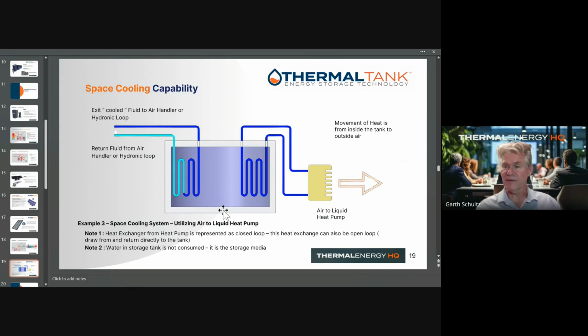And additionally, the buffering in the system allows the heat pump or the chiller that's operating and the air handling unit, it gives buffering so that you don't short cycle the system, where the chiller turns on, turns off in demand to what's happening in the building. So it lengthens that on time, which is the hardest part of running a refrigeration system, is the startup needs of that. So the more consistently and longer time you can operate that by having buffering or storage in the system, that benefits the system the most.